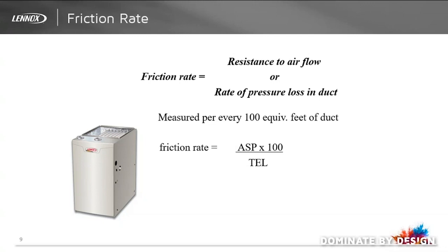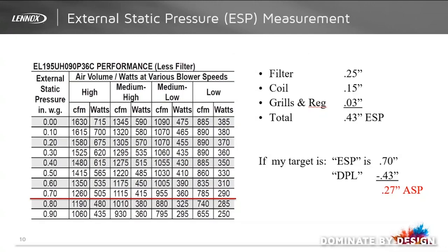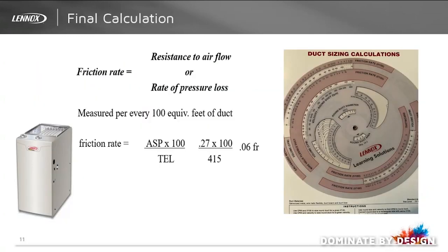Since we have already calculated the total equivalent length, we now need to figure out what the available static will be for the formula. In order to determine available static, we must first determine our target by looking up what speed we need to use and at what external pressure for our given furnace. These performance numbers can be found in the installation or service manuals, also available on LennoxPros in the document library. Once we have our target, we determine the external static pressure drop of devices installed on the system — such as filters, coils, and grills and registers — and subtract that pressure drop from the target to get our available static pressure, or ASP. Putting this into the formula along with the total equivalent length, it comes to a 0.06 friction rate.